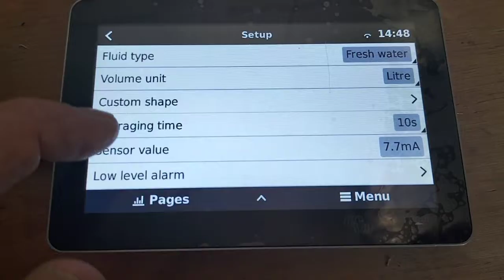Now, so we've set our sensor when empty, sensor value when full by looking at the sensor value at those positions. We've set our capacity type. The other thing we didn't do is we set our capacity, we didn't do sensor type. Now, it can be either a voltage or current. I think default was voltage, but these are a current sensor. Current transducer, not a voltage transducer. So we've set for current. Otherwise, it would be looking at a voltage coming back rather than a milliamps of current.